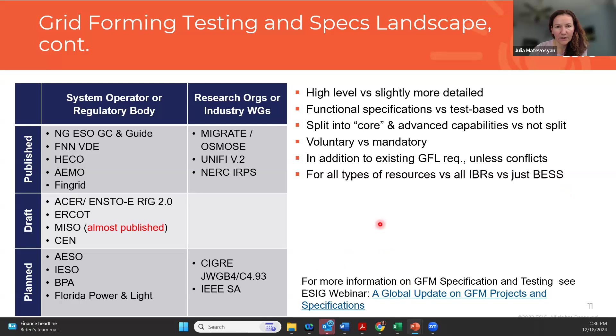So you may ask why grid forming in batteries and not all inverter-based resources. Potentially, you can implement grid forming in any type of inverter-based resource, but grid forming behavior requires a certain amount of energy buffer, which in wind and solar will mean they have to operate below what's available in wind or solar irradiance, and they will lose revenue by operating this way. In addition, grid forming controls in wind turbines require more design considerations because they result in greater mechanical stress, so it needs to be considered from the design stage of a wind turbine.